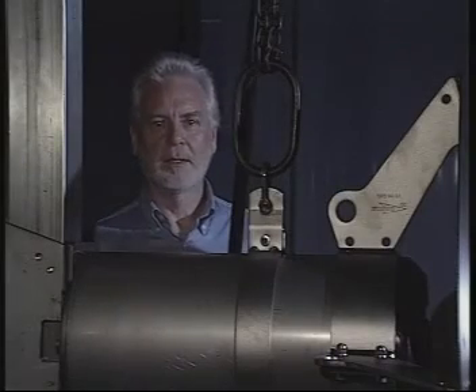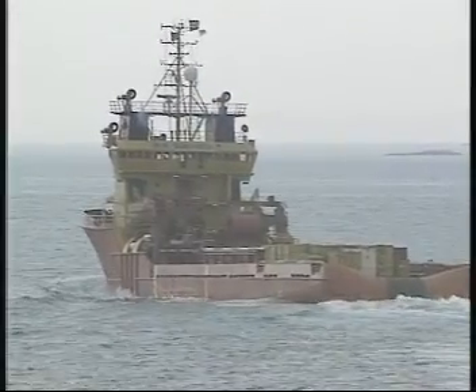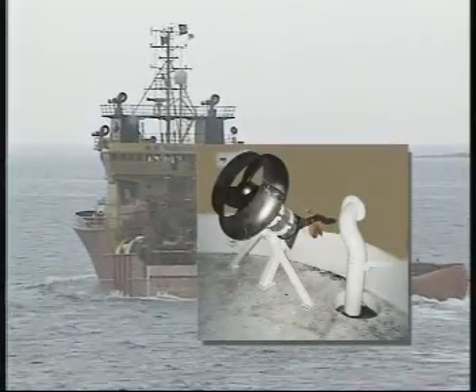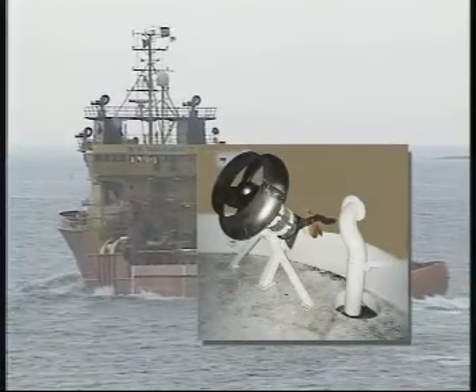Guide bar is the standard installation for Flygt mixers. This is the normal installation method for rigs. In the examples mentioned, guide bar installation can be used only on rigs. Install the mixer so that it's lowered to a physical stop before the propeller hits the bottom of the tank. On supply boats, it's necessary to use a floor stand where the mixer is firmly fixed to the tank floor.